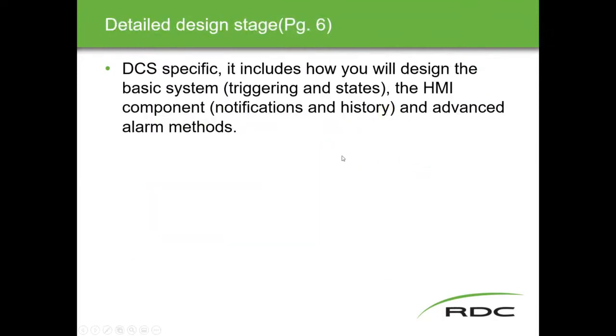The detailed design stage is DCS-specific and includes triggering and state — what items will cause alarms — as well as the HMI component: how to notify operators, how to record history, and how to manage all alarm data being brought in. This involves moving information from the process area into the alarm and data historian areas. Alarm data and historical data are typically on separate servers in a DCS system.